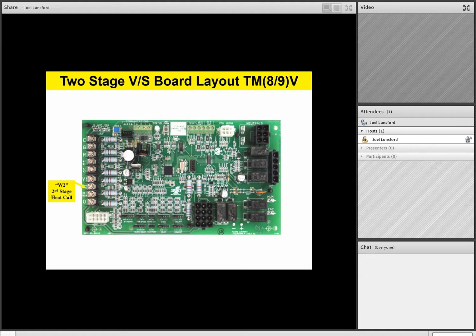Well, this board has some unique functions in the fact that it has a dehume terminal. The dehume terminal allows us to have a standalone humidistat hooked up between R and dehume to provide extra dehumidification. If we enable it, this terminal will slow the fan down to 85% airflow in the cooling mode if it's humid in the house. So we can put a humidistat between the dehume and R terminal, permanently wire that in, and then if it's humid in the space, it'll slow the fan down in the cooling mode to give us extra dehumidification. It's a very, very nice feature.